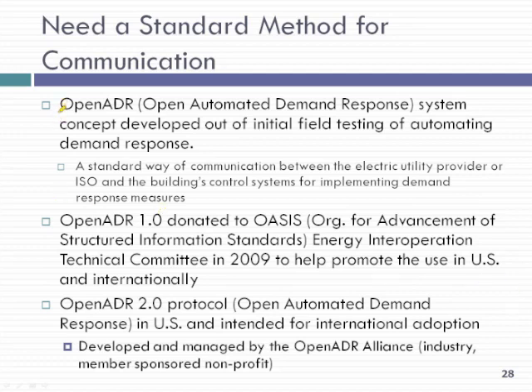There has been development over the last decade or so of what's called Open ADR, Open Automated Demand Response system. It's a standard way of communicating between the utility or provider and the building systems. You could look at it almost like an add-on product for a vendor making a building automation system or energy management system—it's the protocol that defines how the communication happens.